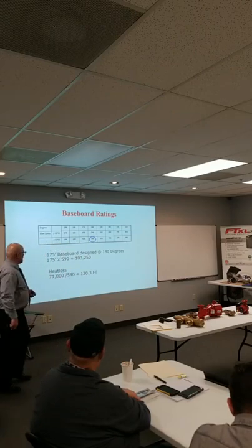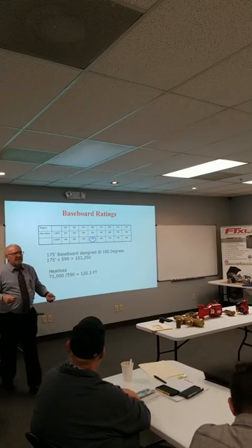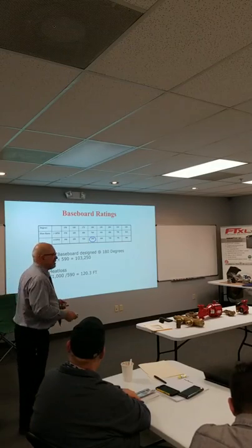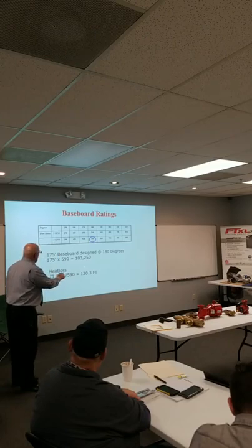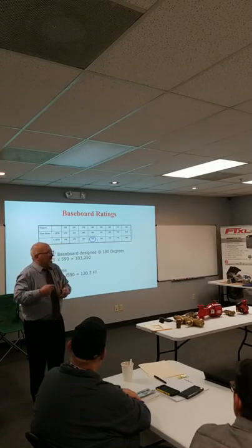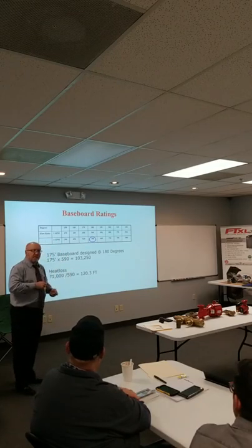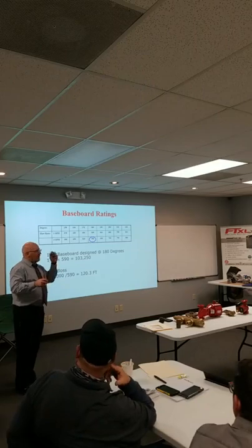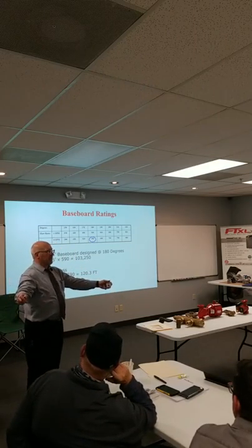So we do the heat loss. We find out we got 71,000 BTUs. If we put that 130,000 BTU boiler in, are we going to get any more output than 71,000? No, we're not. But if we make the calculation backwards, all we needed to heat this house at design was 120 feet of baseboard. So we're not going to pull baseboard out. Absolutely not. But what we can do is, now we're talking about, do I go in with a standard efficient boiler or do I go in with a high efficiency boiler?